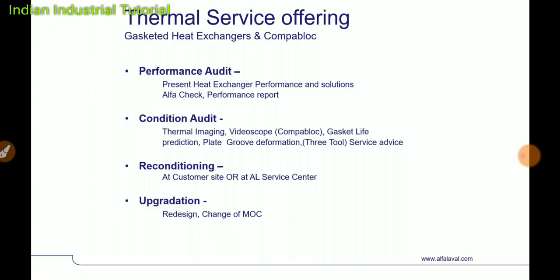We have a gasket life prediction tool and a plate groove deformation tool. These services we can also offer during condition audit. One or two plates from the heat exchangers are already taken during maintenance. We can check those plates, or if the heat exchanger is in open condition, we can check the remaining gasket life and groove deformation, and advise what services this heat exchanger needs.